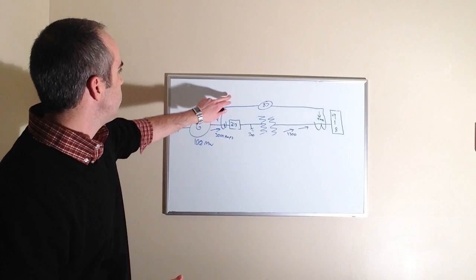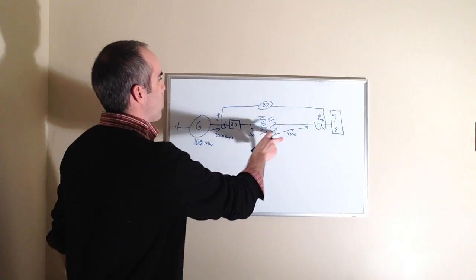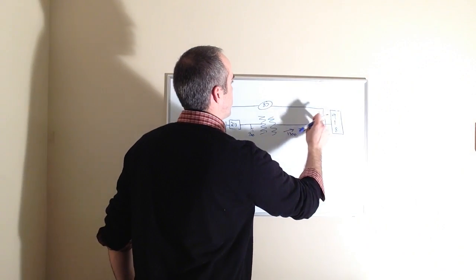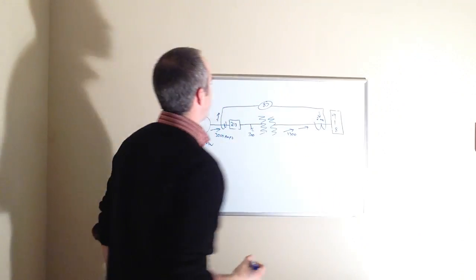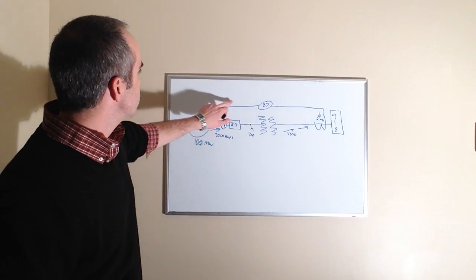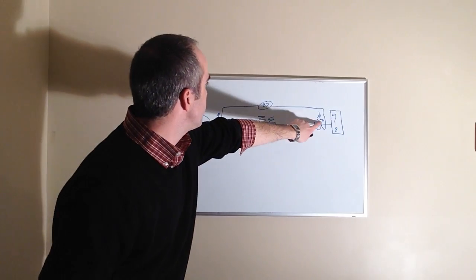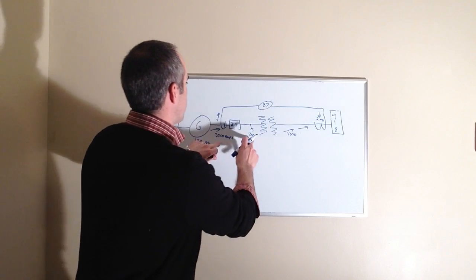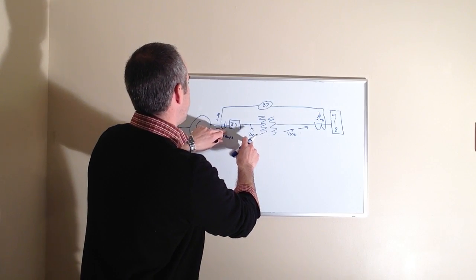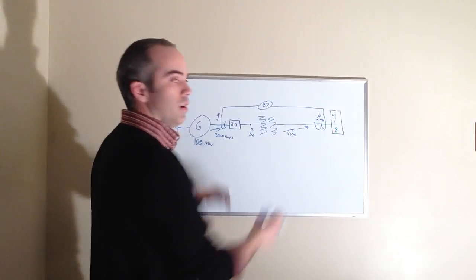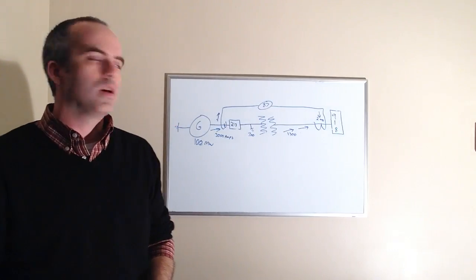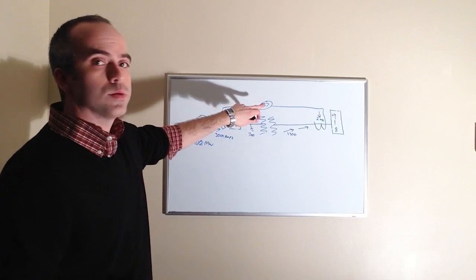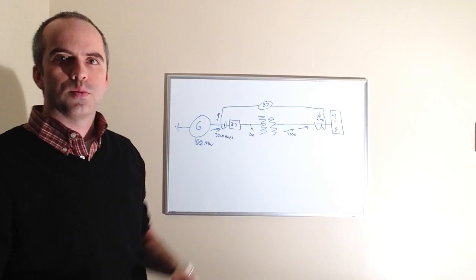So this is not calling for the full 5 amps. We'll just say it's calling for 2 amps. So we've got 5 amps flowing this way, 2 amps flowing this way, so that leaves 3 amps not accounted for. Because we're losing it here, it's seeing the full amount of amp flow here and it's not seeing the full amount here. So there's a difference in the amount of amp flow. That extra amp flow on the secondary that's unbalanced goes through the operating coil of the differential relay, and that's what closes the contacts.